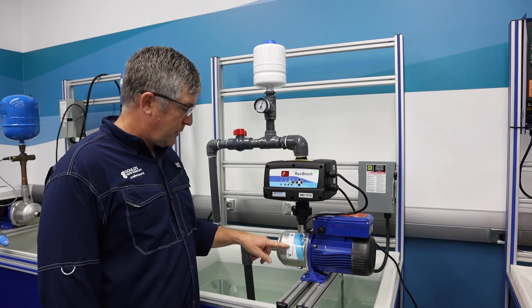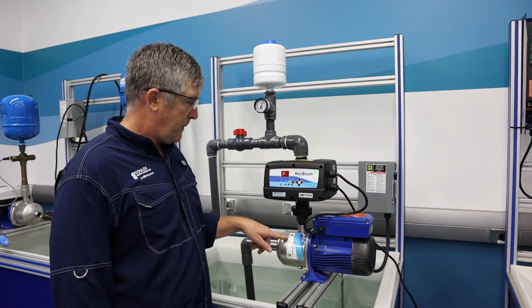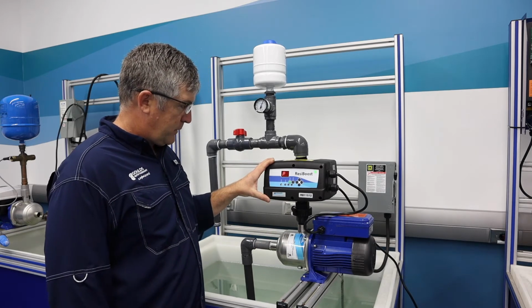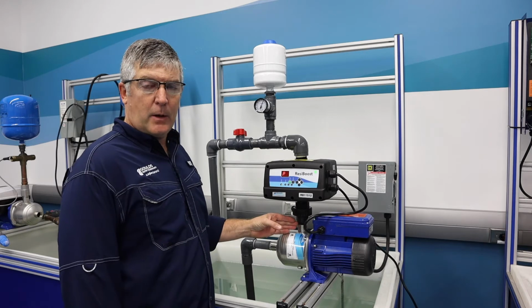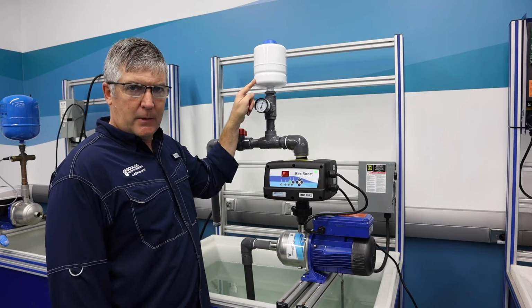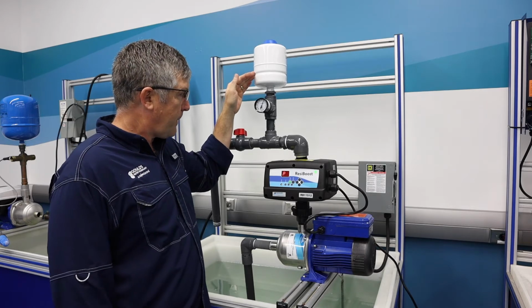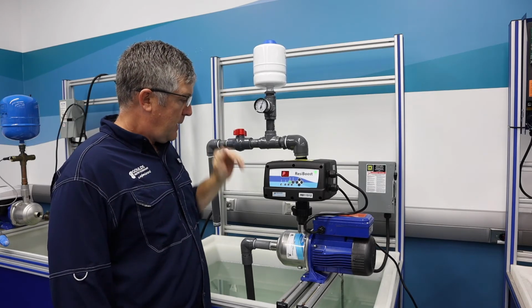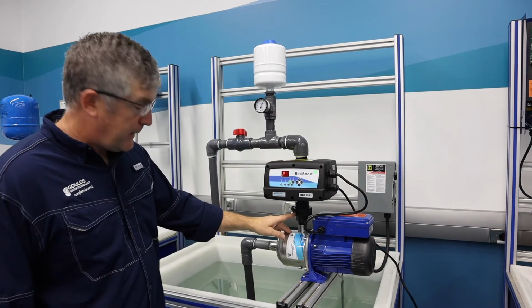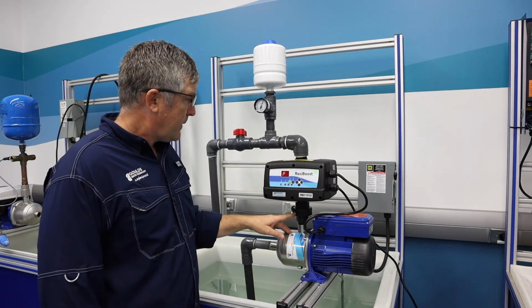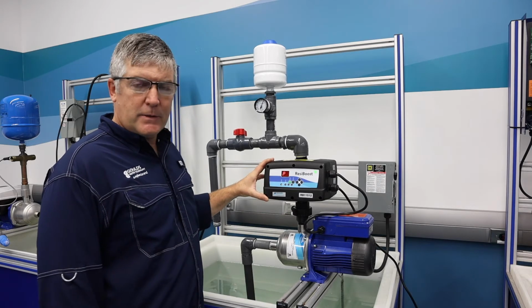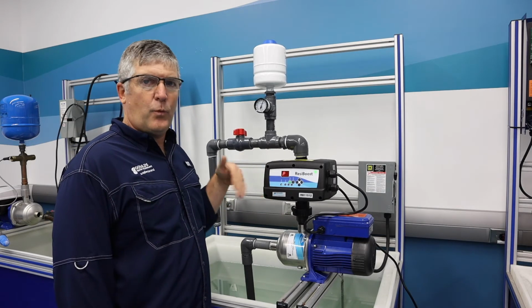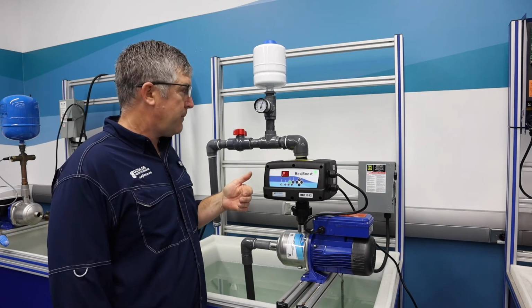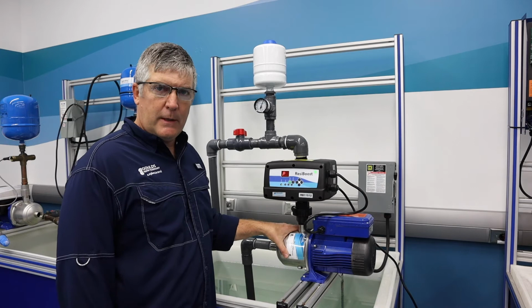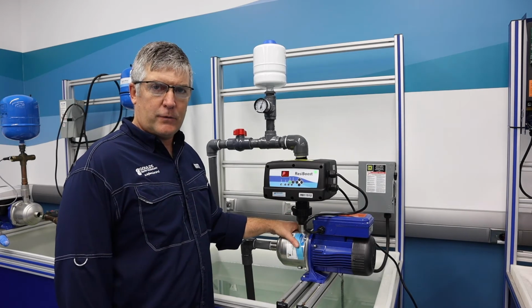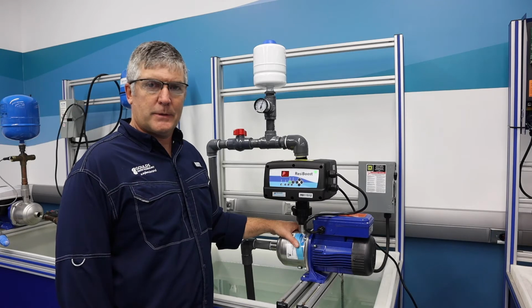So the ResiBoost package system comes with the eHME pump, the ResiBoost unit itself, which is already plumbed up. They come together. And then a separate 2-liter tank, which needs to be installed separately, but does come with the package. A couple things to note here. This does come with a check valve on the discharge side. The transducer is in the ResiBoost itself, so there's no need to separately wire that transducer up. The other thing that's really important is you need a GFCI circuit for this ResiBoost system.